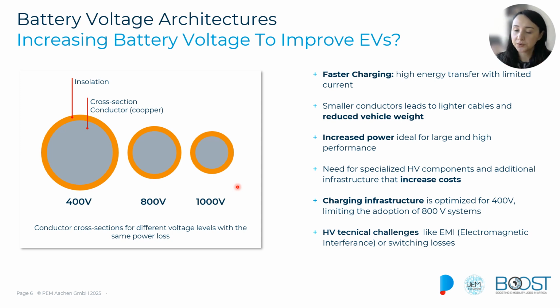For the same power output in the conductor, increasing the voltage allows us to decrease the current. This is because if the voltage increases, the current needed to deliver the same output is reduced, based on the basic power calculation of the system. Lower currents mean less heat generation, because the resistance effect of the wiring will be lower, and this reduces energy loss in our system.